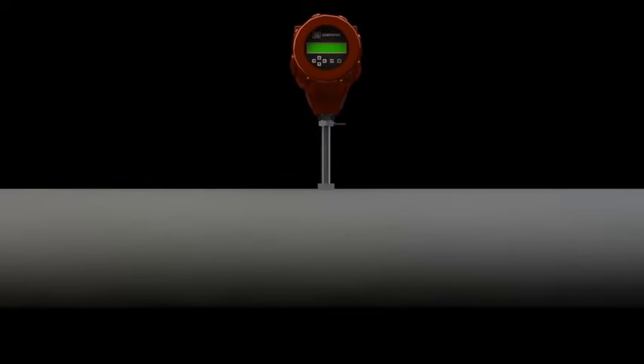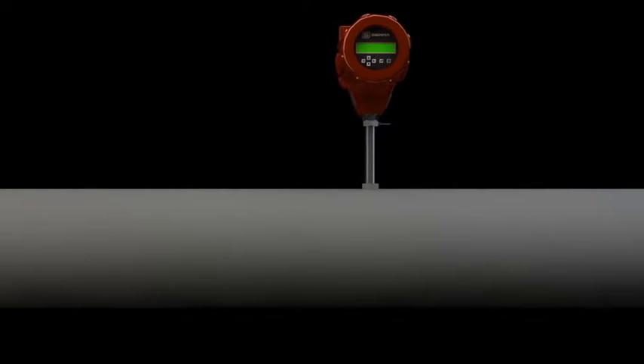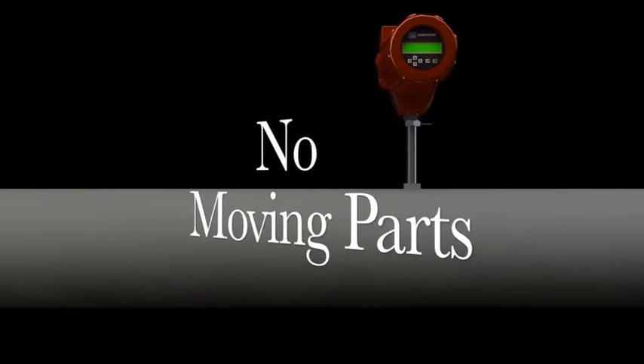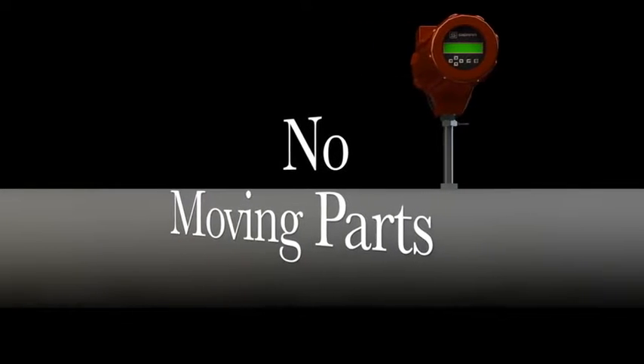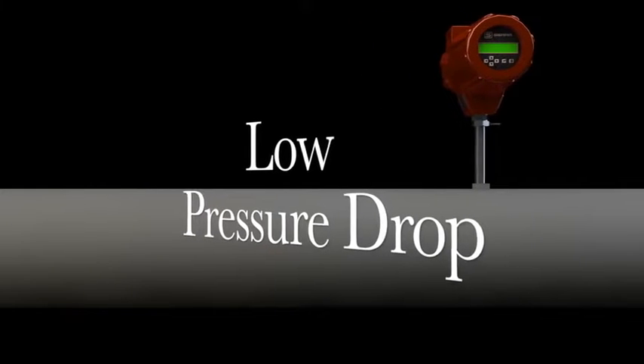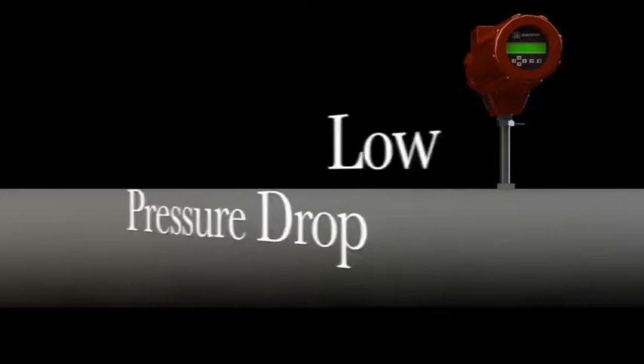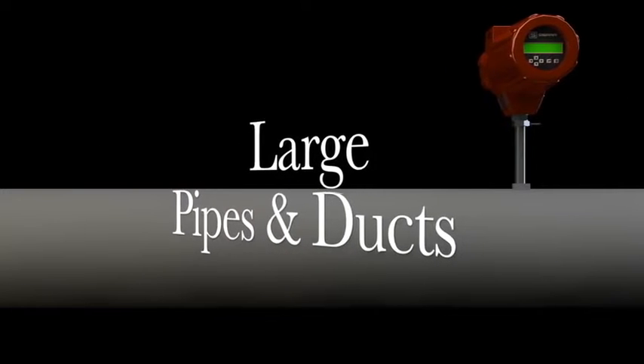with the same instrument. Since they are rugged and reliable, have no moving parts, are easy to insert via hot tap, have negligible pressure drop, and offer an economical solution to large diameter pipes and ducts, thermal technology has been rapidly adopted over the last decade.